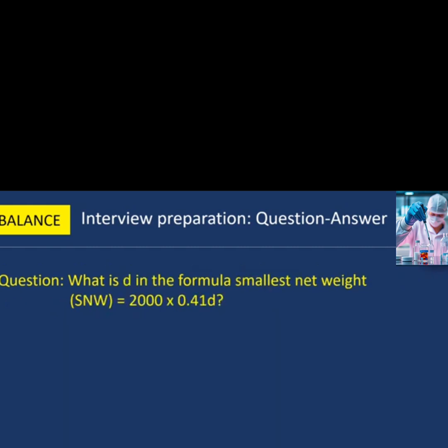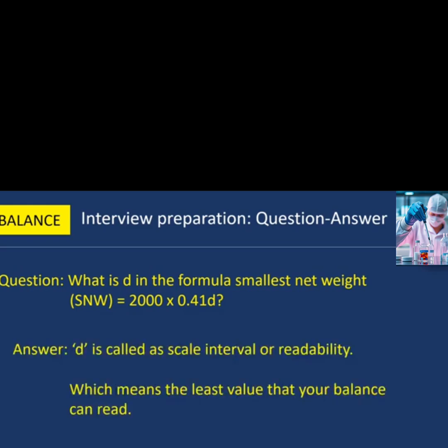Next question: what is D in the formula SNW = 2000 × 0.41D? In this formula, D is called the scale interval or readability, which means the least value that your balance can read.